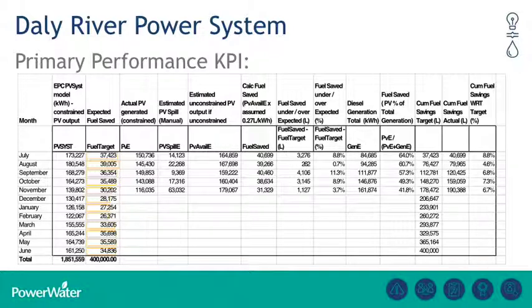The key numbers to look at are in the 4th column on the right—that's the fuel savings, calculated purely as energy delivered by PV versus the entire load. In July, this financial year, we were saving about 64%. In the latest month, November, we've had the PV array offline for a week for some servicing work. But in the far column, you can see we're trending ahead of our model—currently about 7% ahead of where we thought we'd be.